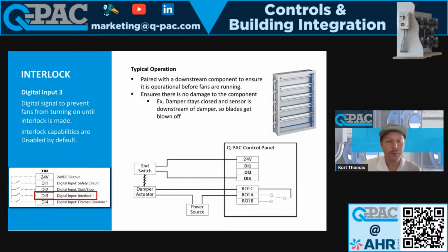Interlock. So I think our interlock function actually works very well. I think it's best for critical applications. That way you don't have to rely on your building automation system to make sure that a damper is open before we turn the fan, so you don't blow out any blades, right? If you want to, so this is how it functions.